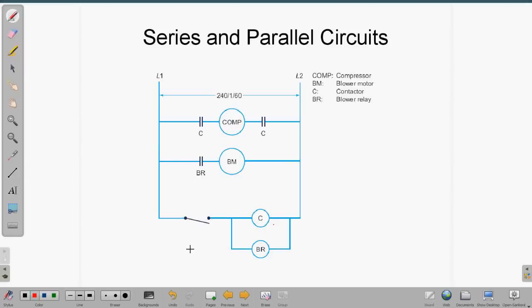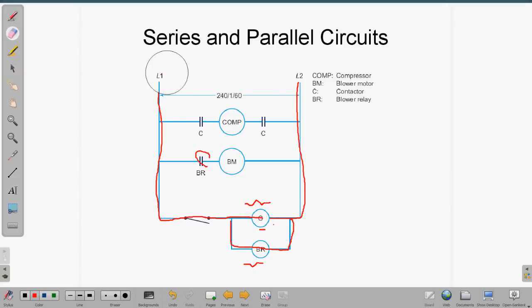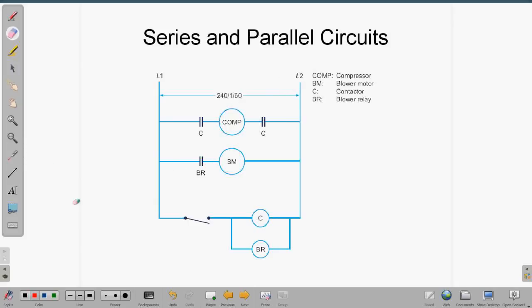Here we have three complete circuits, and they all have the four things in common: line, power, switch, and load. The contactor coil energizes the contactor, and the blower relay coil energizes the blower relay that controls the contacts. In this case the switch would probably be a manual switch. The contactor coil and the blower relay coil are your loads in the control circuit. All three complete circuits have power, line, switch, and load.